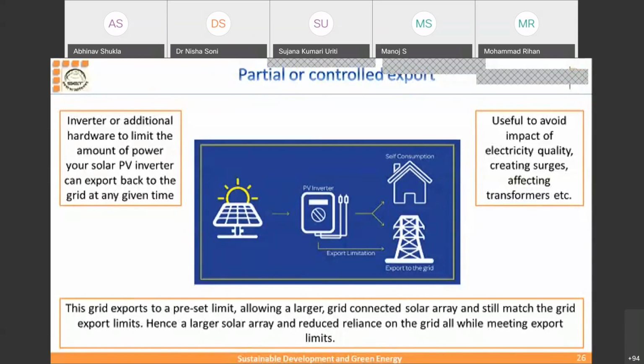For example, in Gujarat they have a DTR capacity limit of 60%. So if you have a distribution transformer of 100 kVA, you cannot go beyond a 60 kVA solar plant, or 60 kVA of power exported by the solar plant. Their intention is to restrict more power than 60 kVA going into the electrical network.